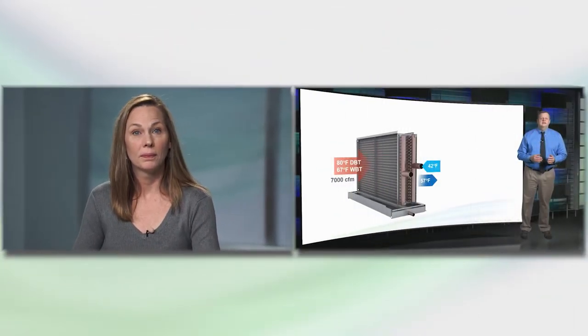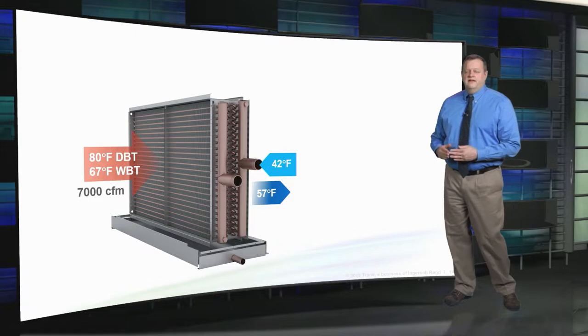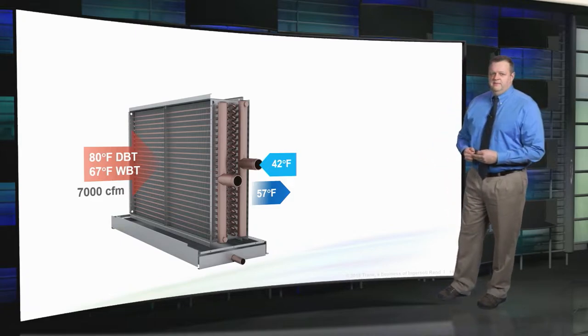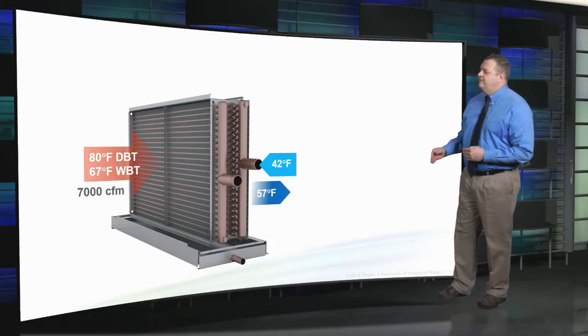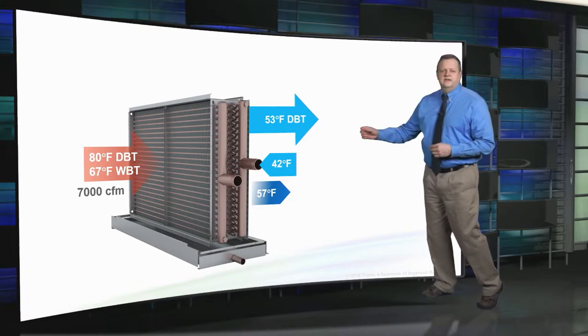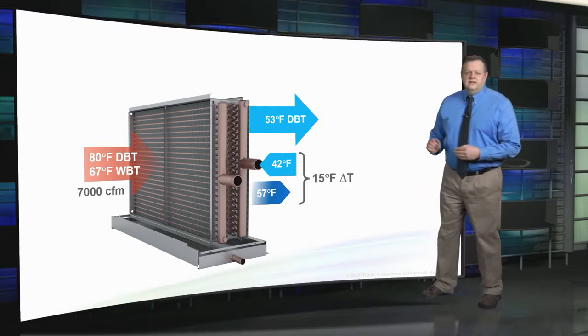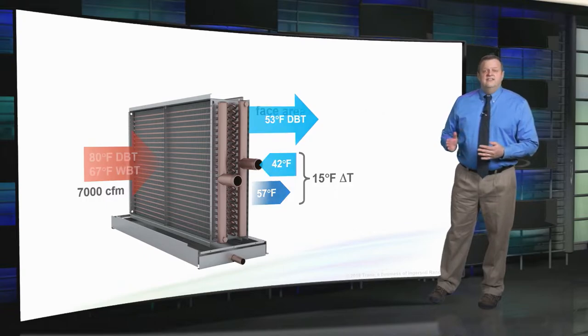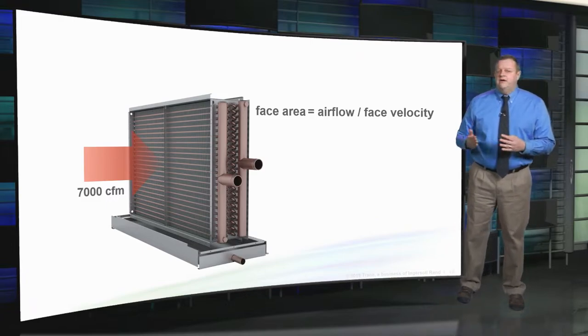Now given this new requirement, let's look at the process for selecting chilled water coils to achieve at least a 15 degree delta T. To demonstrate, let's look at an example chilled water coil selection. This coil is installed in a mixed air VAV air handler with a design supply airflow of 7000 CFM. The mixed air enters the coil at 80 degrees dry bulb and 67 wet bulb, and this air needs to be cooled and dehumidified to 53 degrees leaving the coil.